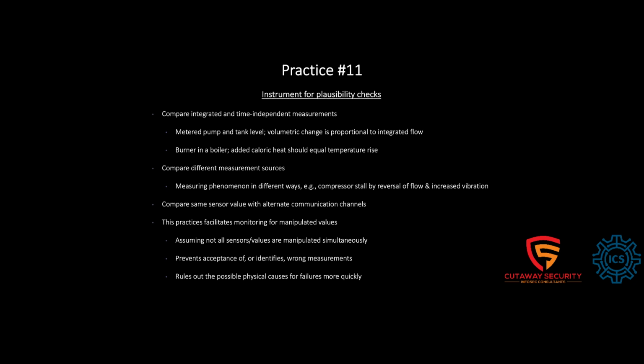The device will check and protect itself. And we need to understand that when we're talking about risk around being able to manipulate some of those values. Yeah, that's a great point, Don, because I hear a lot of people talking about how they can easily manipulate values on a Modbus register. Oh yeah, I'm going to be able to force this tank level to 50%, but the tank is overflowing.